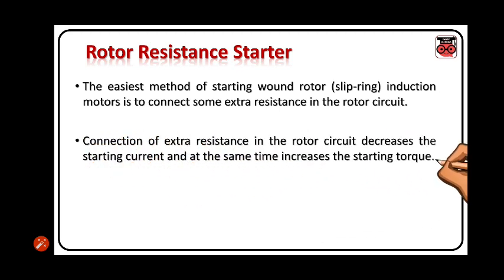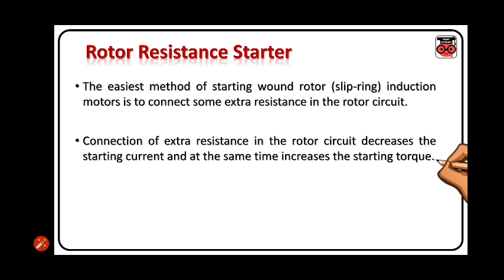Rotor Resistance Starter. The easiest method of starting wound rotor induction motors is to connect some extra resistance in the rotor circuit. Connection of extra resistance in the rotor circuit decreases the starting current and at the same time increases the starting torque.